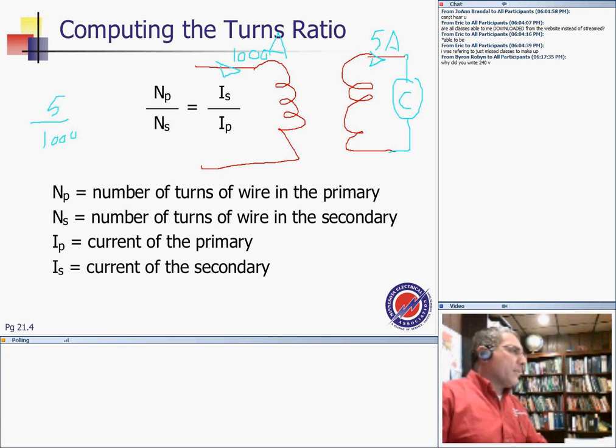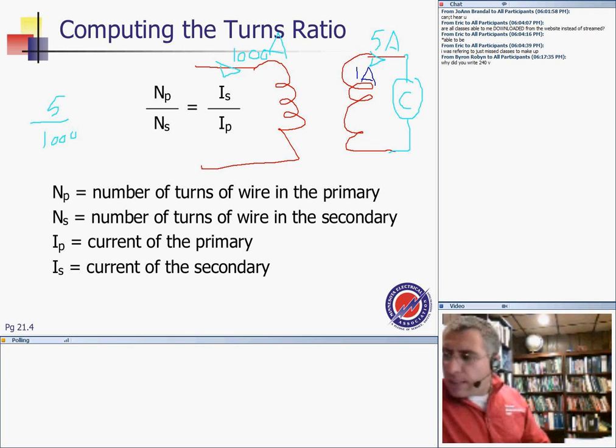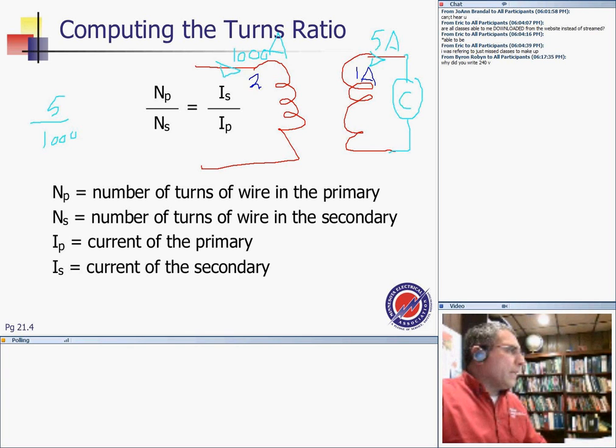transformer, current transformer. The current transformer, every 1,000 amps will be seen on the secondary as 5 amps. So 1 amp here in reality will be seen by how much? 200 amps. So every 200 amps here will be seen as 1 amp. That gives you the ratio of the transformer. That's the only way, my friend, guys, we can measure high current.